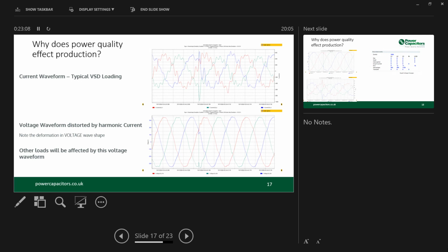What we've got here is an inverter not quite firing properly. What that does is it distorts this waveform. What we want from this waveform is a nice sine wave. You can already see that the distortion here is causing distortion on the nice sine waves. Got bumps there, but here we've got a huge distortion. Problem with this is that instead of having a nice voltage going around like that, we're losing those volts.